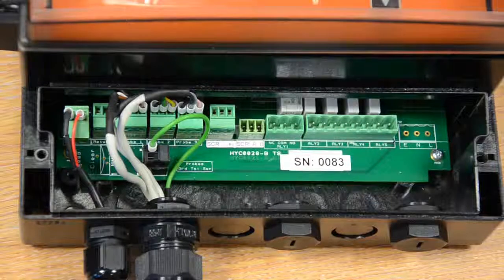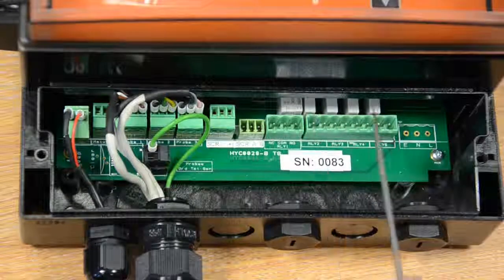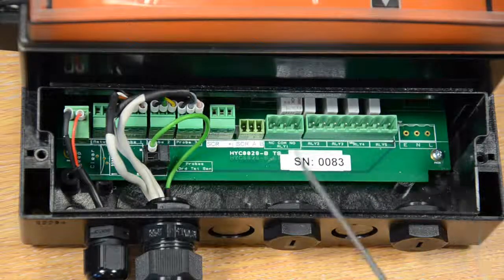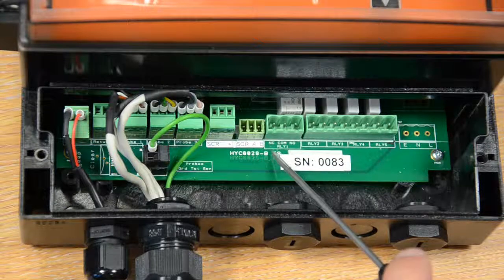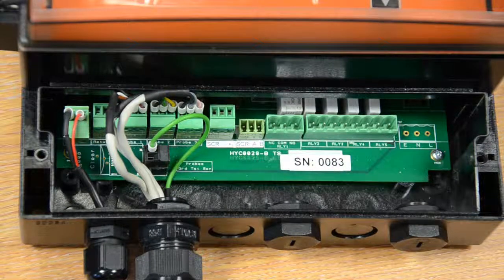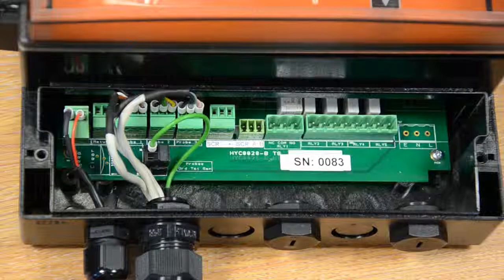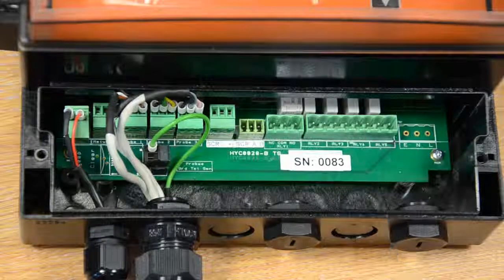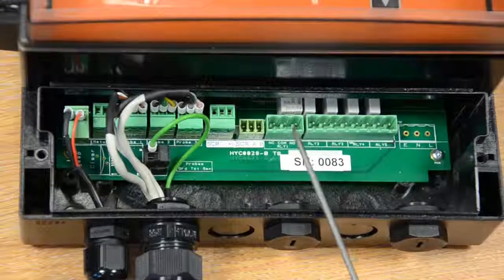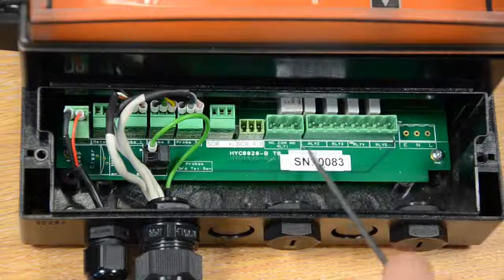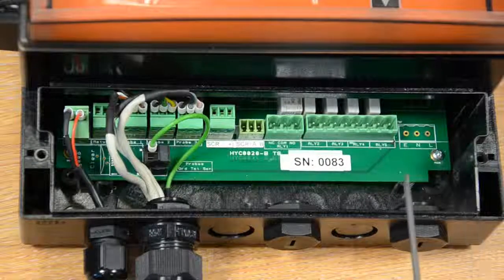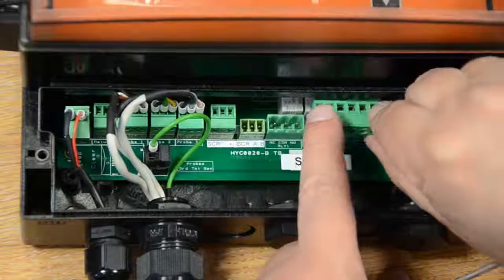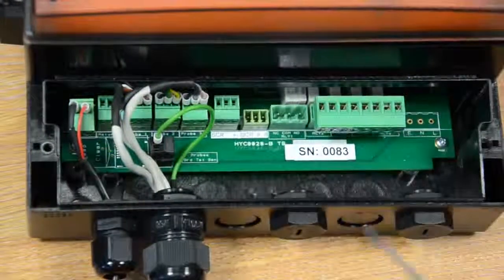Earth returns at TB11. So on TB8 and 9 we have our relays. You'll notice TB8 is a changeover relay and has a common. Relays 2 to 5 have this, and it's normally open. But there are options for normally energized and normally de-energized in the settings on the controller itself. So as you can see, there's only 2 terminals for each cable. These relays are normally open. So next we'll talk about the probe wiring.